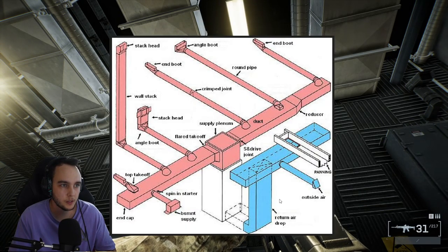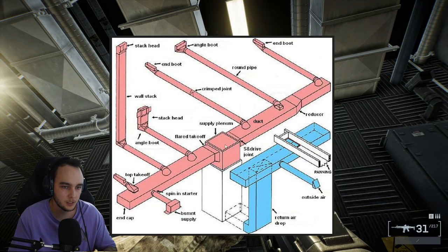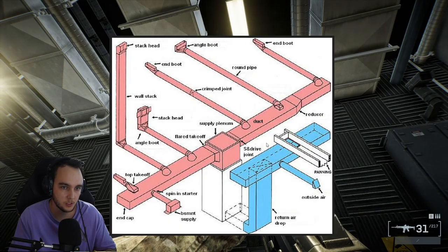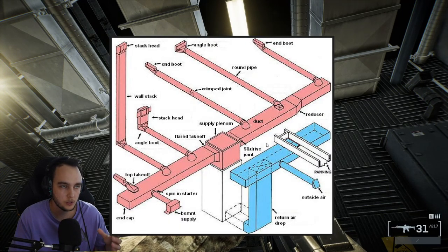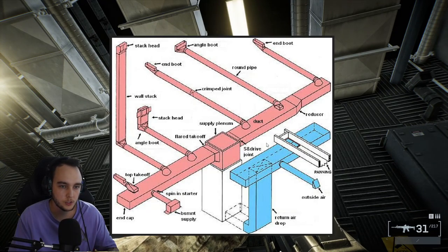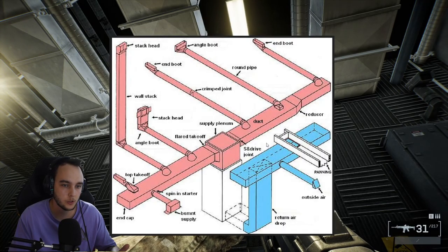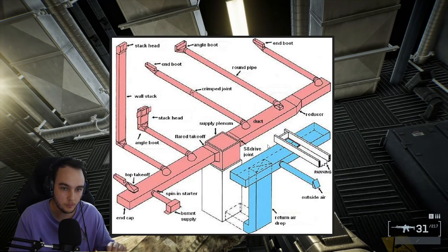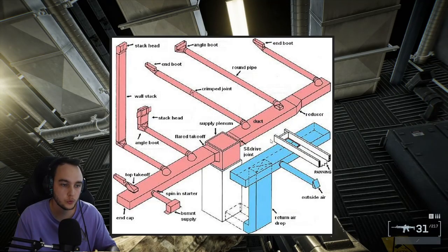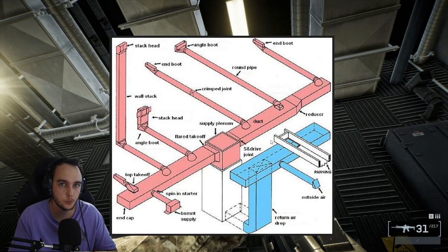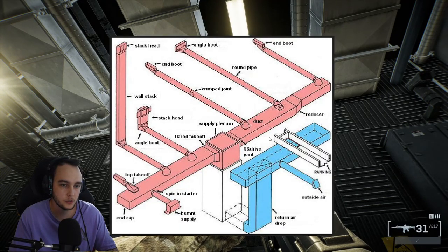You'll also have something that's called exhaust air. Now that is air that just directly leaves the building. It doesn't get mixed into anything, doesn't come back into the building, doesn't get redistributed, nothing. So that's stuff like your washroom exhaust fans, or if you have a laundry system like a washer and dryer, that's your dryer exhaust that just goes right out of the building. So when you get to more commercial buildings like a laboratory, you'll see that in fume hoods or systems like that. Things that are actively extracting gases or other fumes you don't want to be breathing, basically, right?